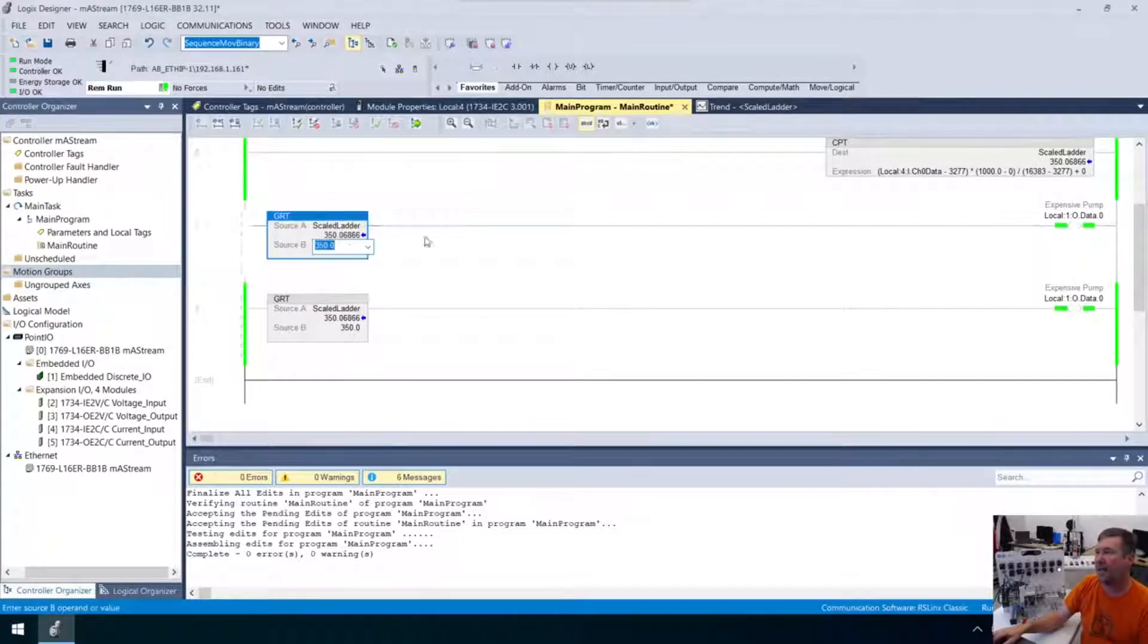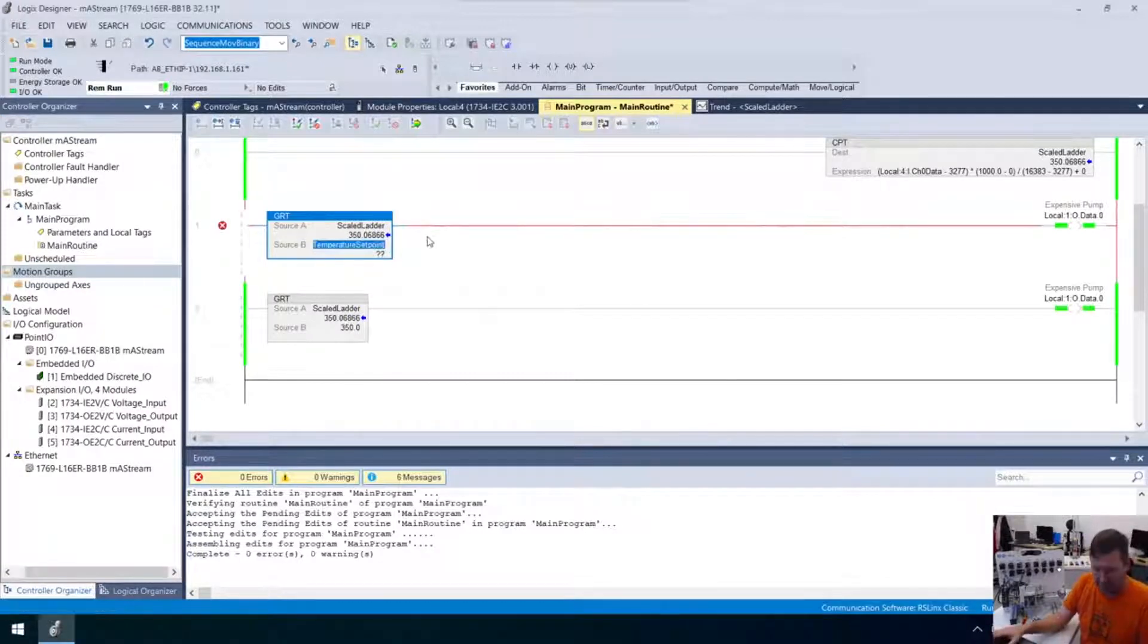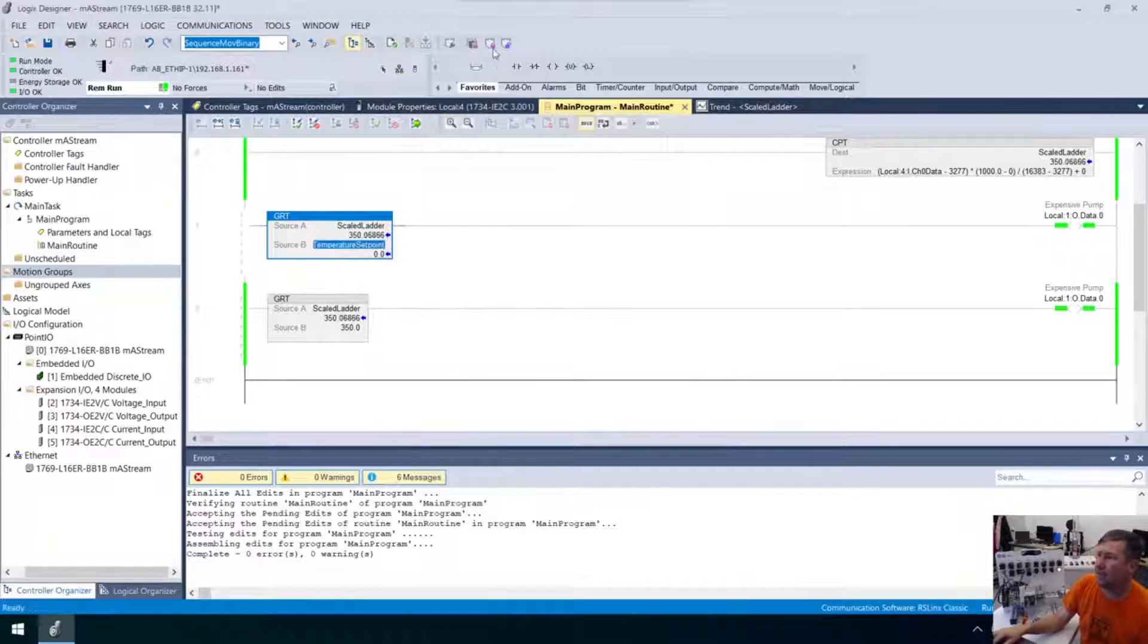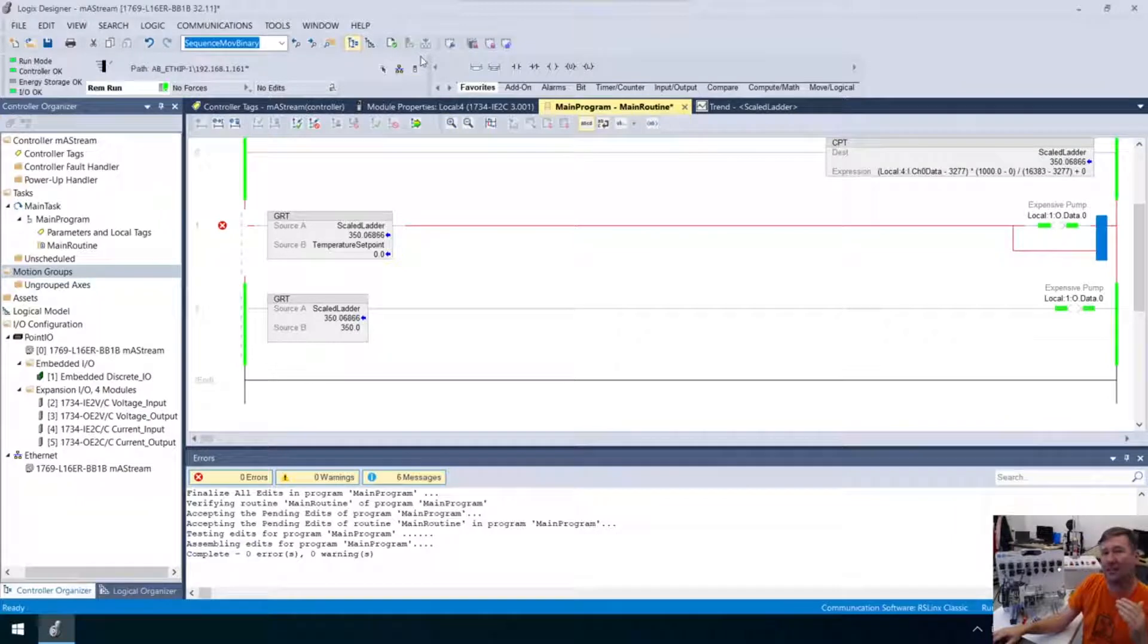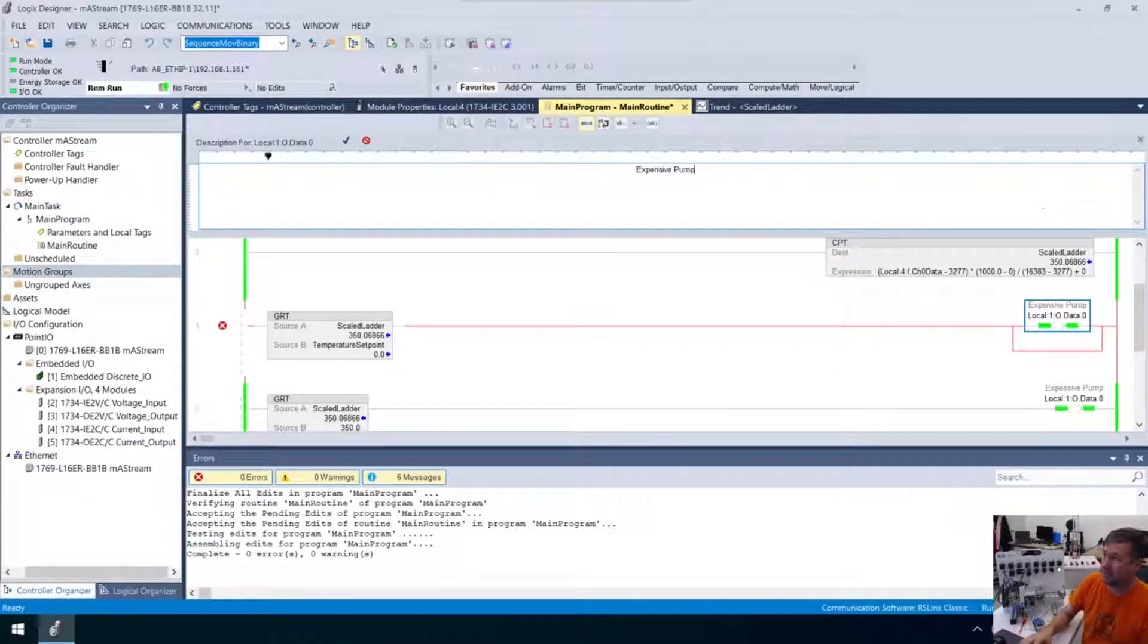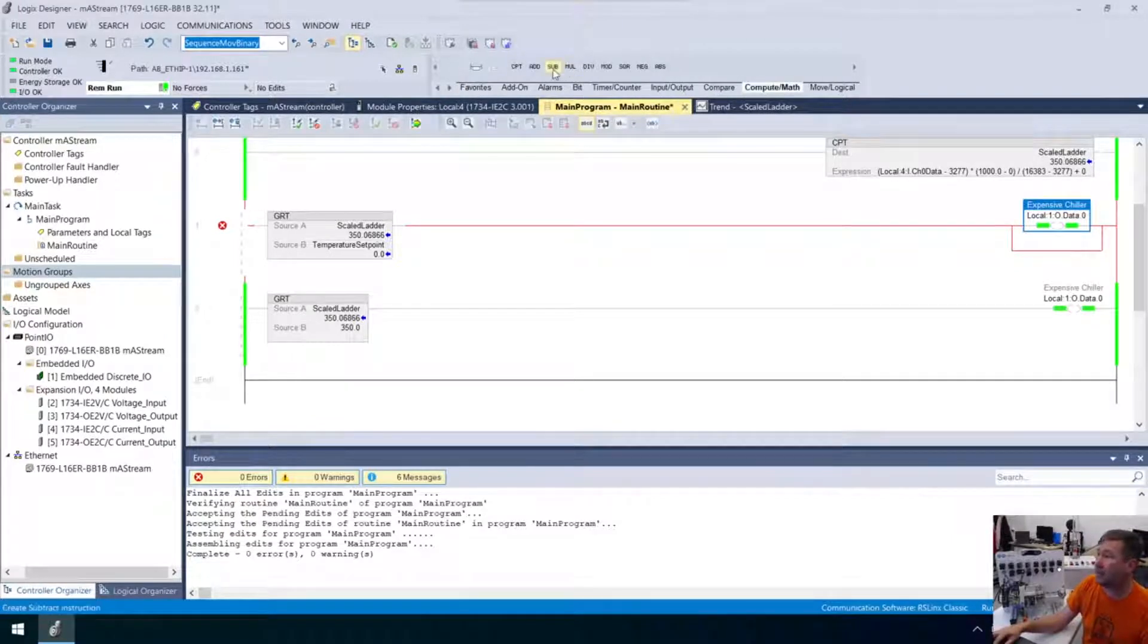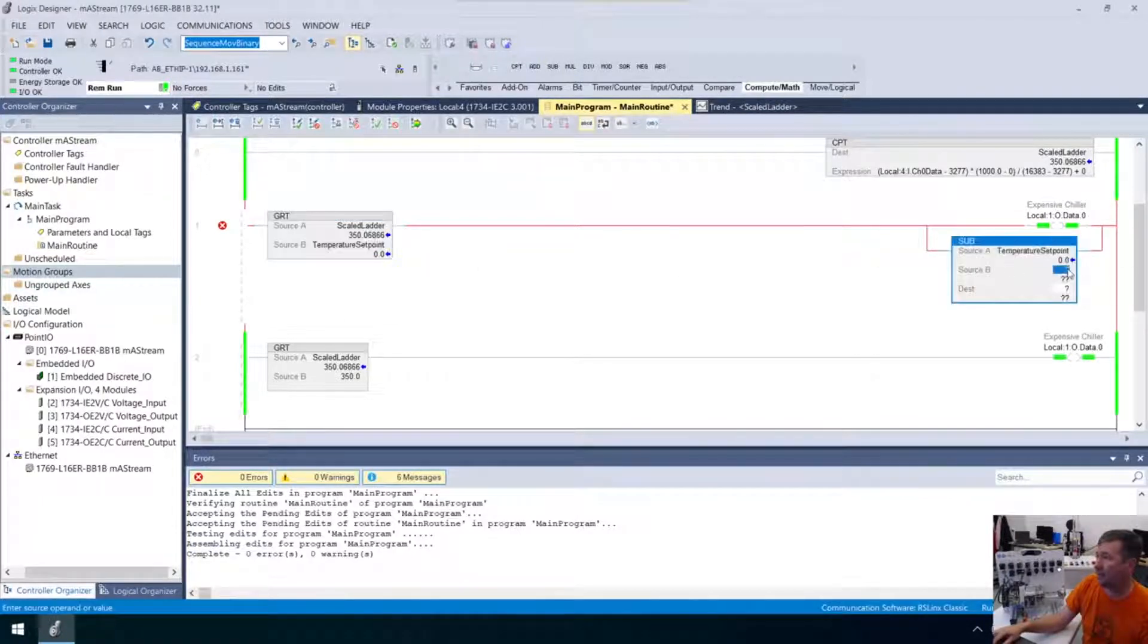Then we went through the LIM instruction. That's not going to work. So here we're going to use this, what we call a span, but we don't want the operator to enter the second value. So first we need a value here. And let's make this our temperature set point. And we're going to need to create that. And we want this to be a real that we can enter a decimal if we wanted to. But now what we want to do is we're going to add something else because what we need to do is when we, this heat, or sorry, in this case, we're chilling. I gotta make sure I get this, I always get this backwards. We're going to use this subtract. We want it to cool a little further before we shut our chiller off.